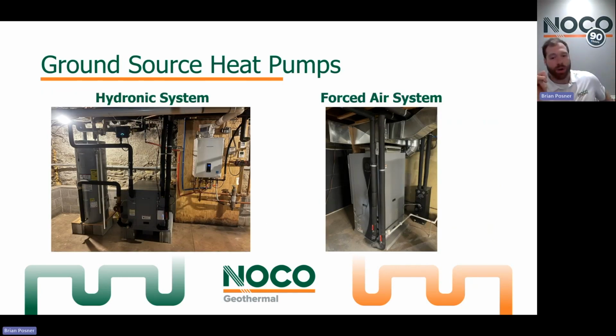Now, the interior equipment, what those pipes get connected to. That's what's on the screen right now. Those are the physical heat pumps themselves. Now, what you have on screen are a hydronic and a forced air version of these. So say you have a furnace and ductwork in your home. You get your heating and/or cooling from forced air.